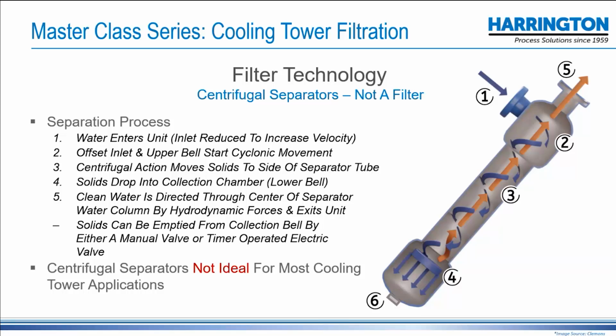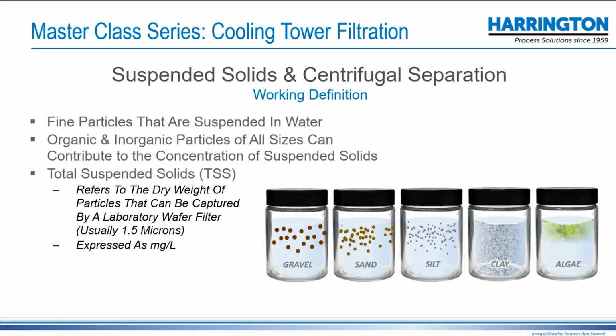Now, these are great. For instance, if you have a well that's producing sand and you don't want to put it into a pressure bladder tank or pressure vessel, you can run it through a centrifugal separator. It'll draw out the sand. You don't need a more advanced screen for that. These are not ideal for cooling tower operations because they are dependent on the weight of the solids. And solids come in all types and kinds. You have gravel, sand, fine silt, which is very light and usually is entrained in the water, clays, algae. Well, a centrifugal separator will not remove anything that has a specific gravity under about 2.2.